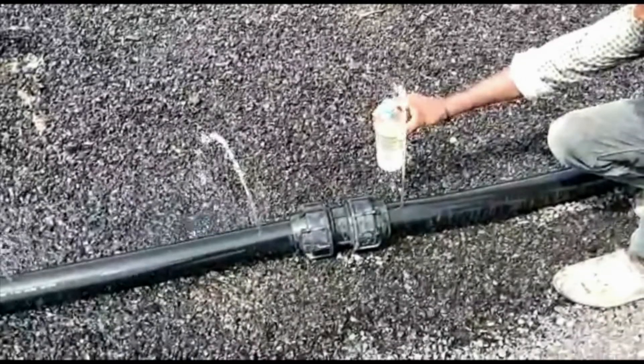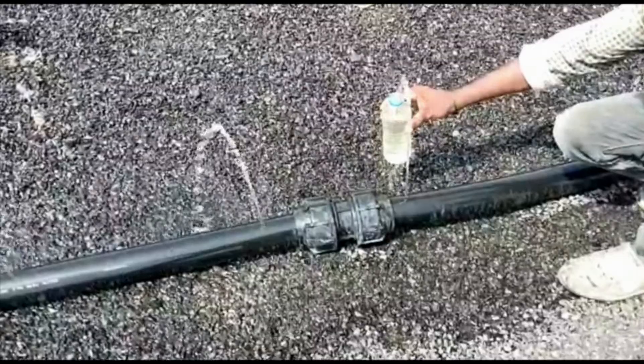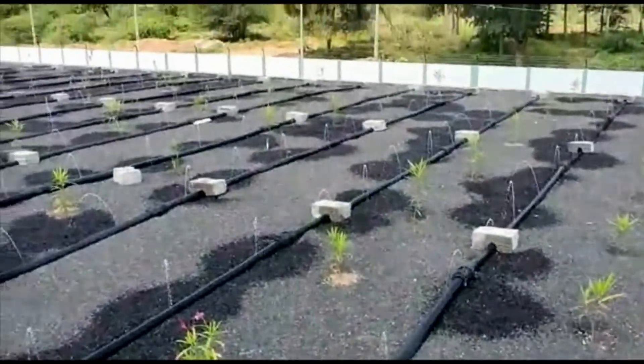We will have a look at some real-time samples collected after each stage at the end of the video. After percolation through BM1, the resultant nitrified water is collected in a collection tank and is then pumped to BM2, where the nitrified water and the ammonical water from the tube settler percolate through and are collected in the chlorine contact tank.